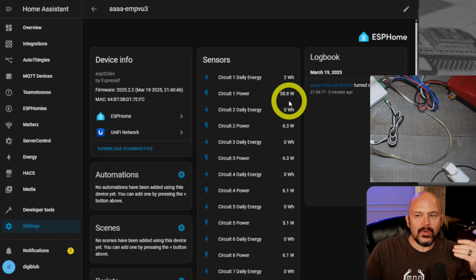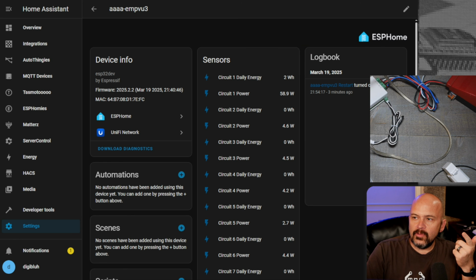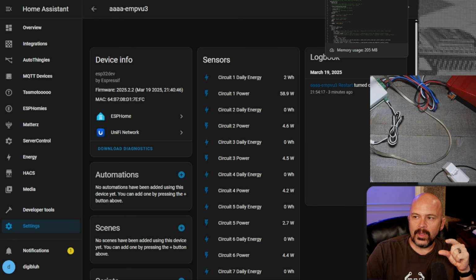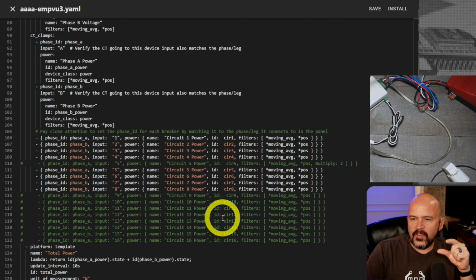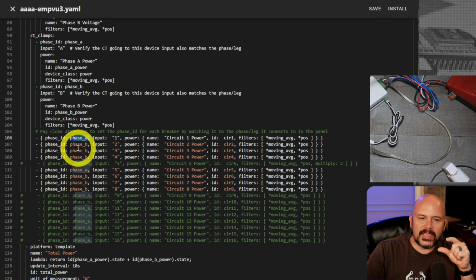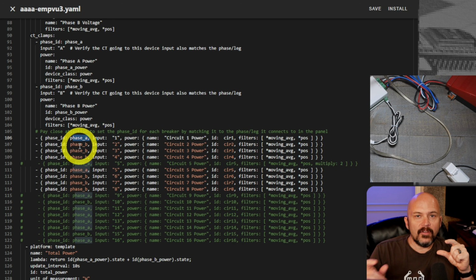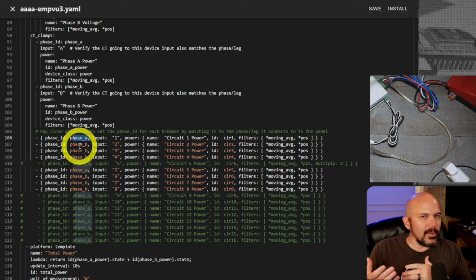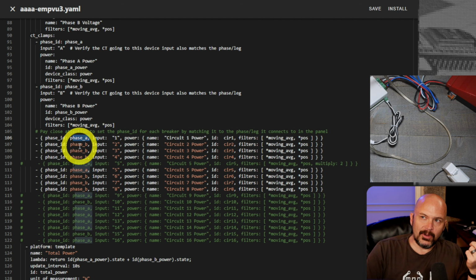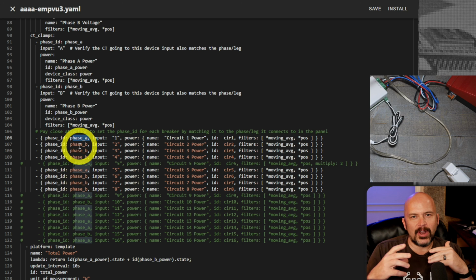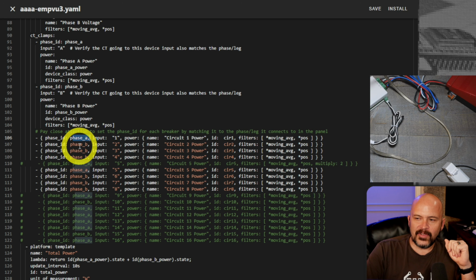Once you go through and install everything and install your clamps, you can screw up the direction on clamps 1 through 16. In the config itself, you can actually change, hey, this one's assigned to phase A, this one's assigned to phase B for the voltage reference. That doesn't really apply for people doing 3-phase power, so you do need to make sure your clamps and voltage references are correct. US people, if you get it backwards, you can just use the other voltage reference because it's 180 degrees out of phase from each other.